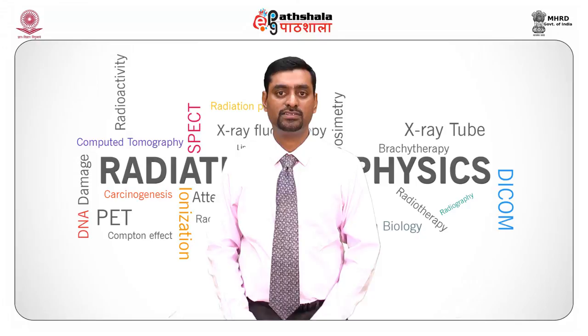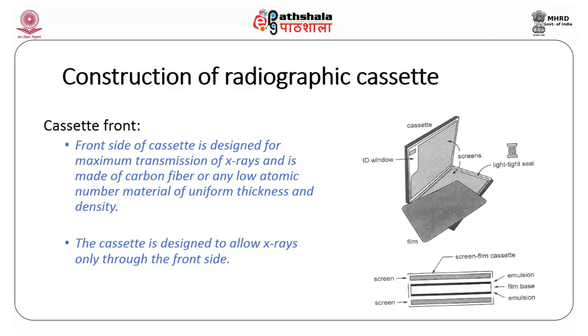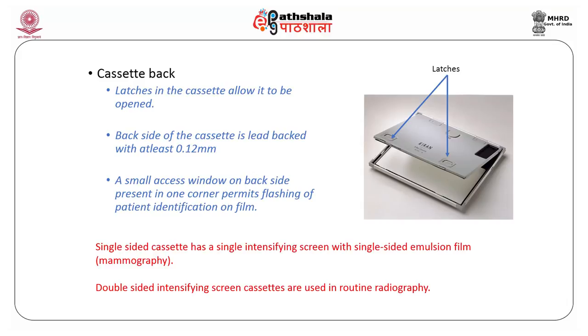Let us go into detail about the construction of the radiographic cassette. The front of the cassette is designed for maximum transmission of X-rays and is made of carbon fiber or other low atomic number material of uniform thickness and density. The back side of the cassette is lead-backed with at least 0.12 mm of lead so that backscatter radiation does not come in. A small access window on the back side in one corner permits flashing of patient identification on the film. Single-sided cassettes with a single intensifying screen and single-sided emulsion film are used for mammography, while double-sided intensifying screens are used for routine radiography.